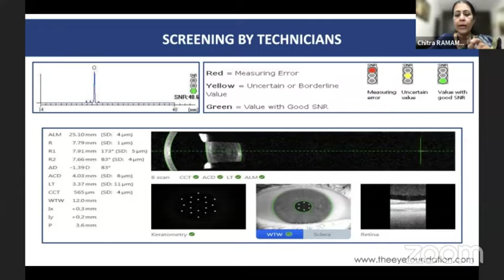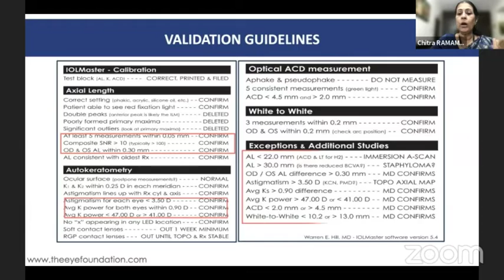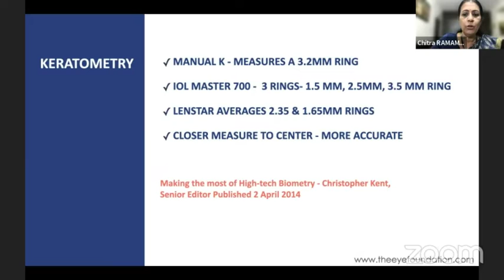But having said that, if the astigmatic difference is more than 3 to 3.5 diopters, or if the IOL power or the ACD between the two eyes is different, we need to go back and do a remeasurement before we take that as a final value. In fact, for keratometry, it makes sense to do it in two or more instruments because each of them measures at a different point. The manual K is at a 3.2 ring, the IOL Master measures in 3 rings, the Lenstar in 2 rings. And what we need to remember is that the closer to the center you measure, the more accurate you are.